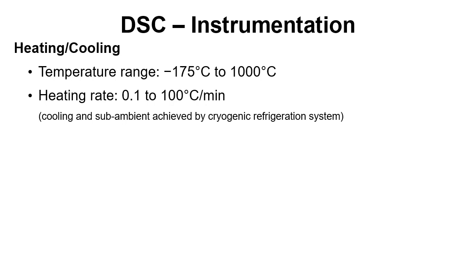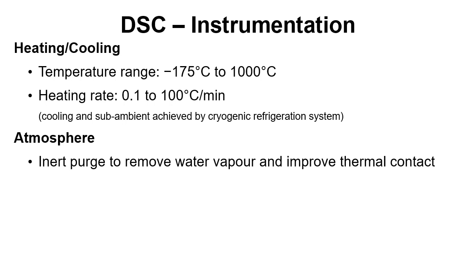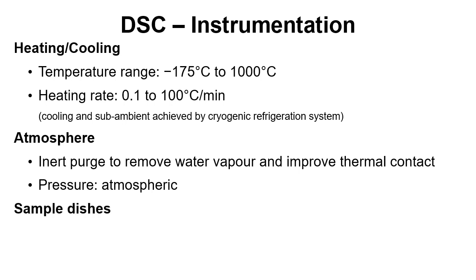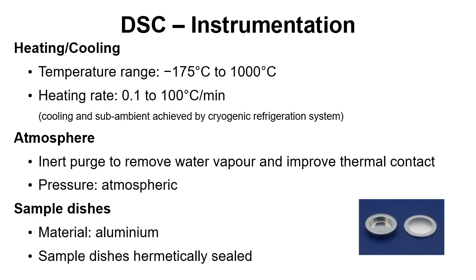For sub-ambient temperatures a cryogenic refrigeration system is required. In terms of atmosphere, an inert gas can flow through to remove water vapour and to improve thermal contact, and the instrument is typically run under atmospheric pressure. Sample dishes are normally made of aluminium and are hermetically sealed — a base and a lid are crimped together once the sample or reference is inside. The lid can also be pierced if it needs to be open to the atmosphere.